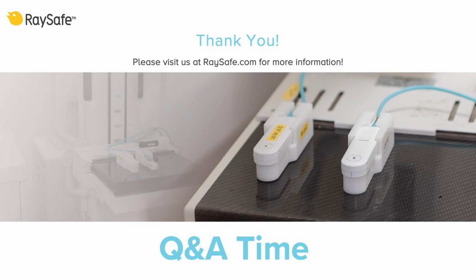Can the 452 be used for in-beam measurements, like in the radiation field of an X-ray machine? No, I would not recommend that, to be honest. The intention of the 452 is more for scatter radiation and leakage and things like that. So I wouldn't recommend using it in the primary X-ray beam.